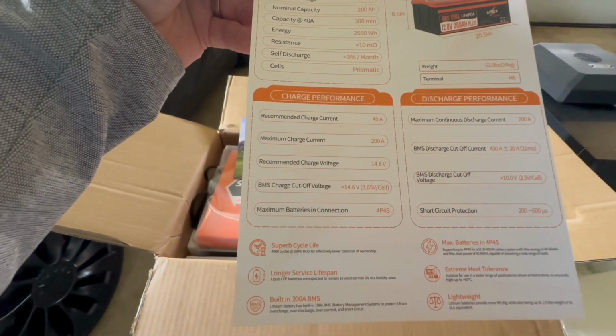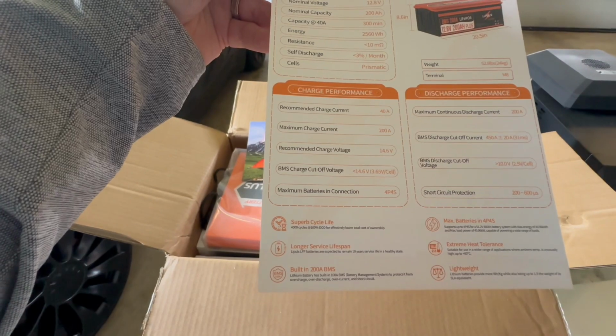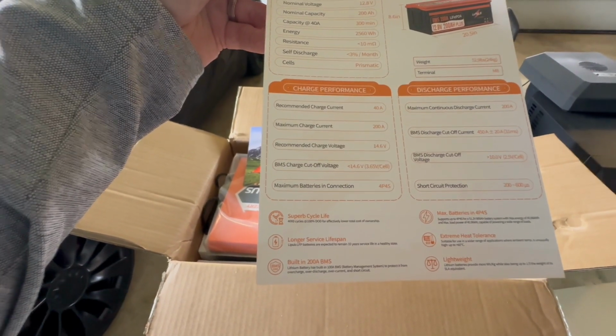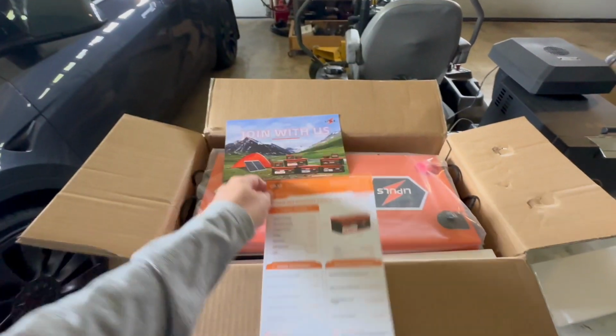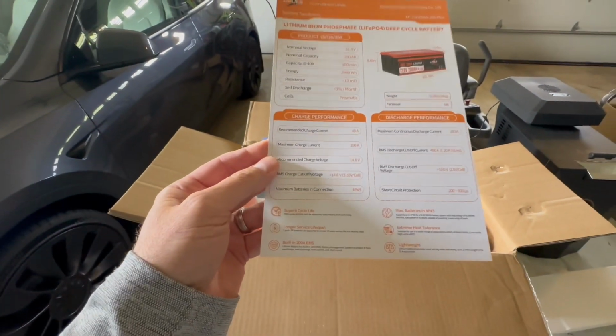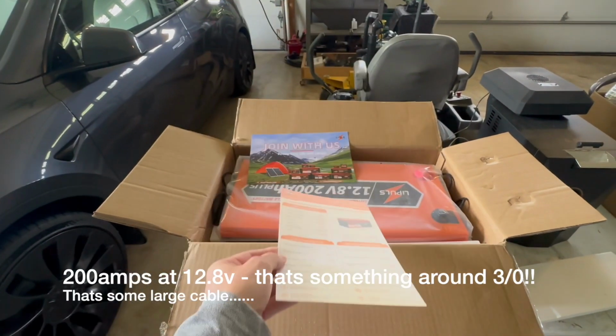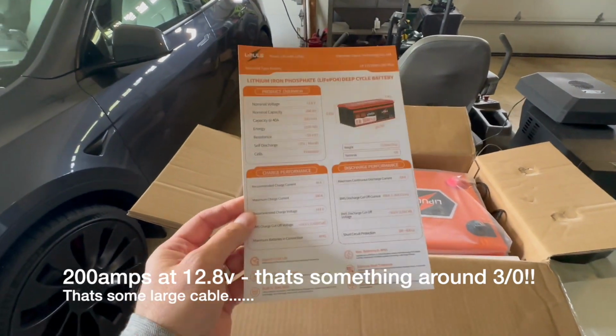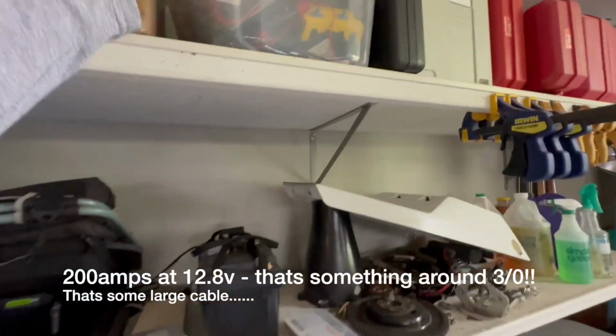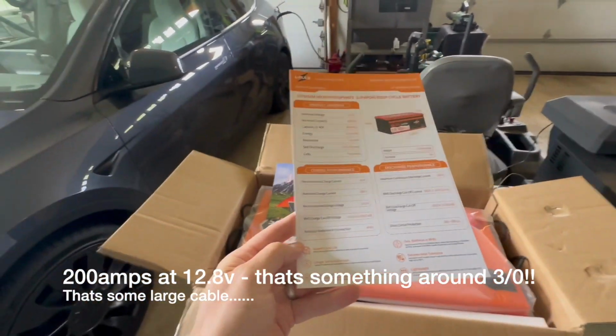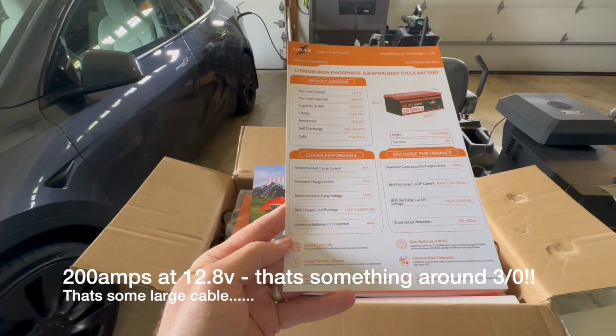Recommended charge current is 40 amps, maximum charge current is 200. That's quite a bit, which for a 200 amp battery, that's going to require some big wire to pull. I do have some wire up top here, it's freaking thick. So once you start pulling 200 amps of power, that's a lot.